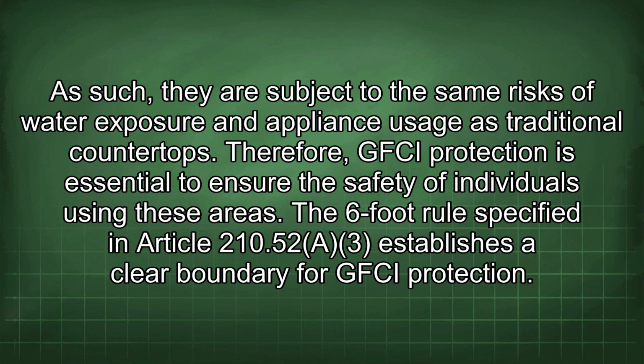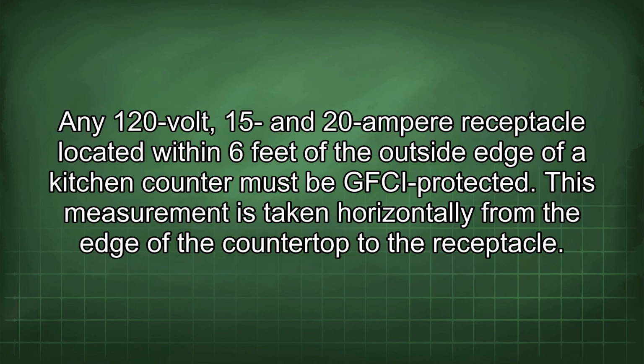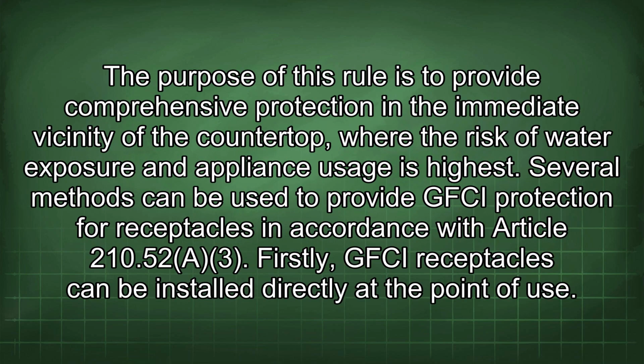The 6-foot rule specified in Article 210.52(A)(3) establishes a clear boundary for GFCI protection. Any 120-volt, 15 and 20 ampere receptacle located within 6 feet of the outside edge of a kitchen counter must be GFCI protected. This measurement is taken horizontally from the edge of the countertop to the receptacle. The purpose of this rule is to provide comprehensive protection in the immediate vicinity of the countertop, where the risk of water exposure and appliance usage is highest.